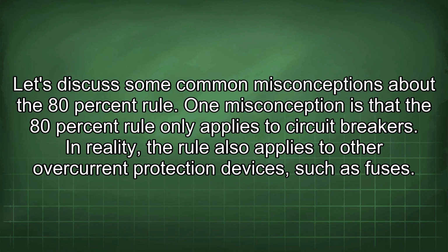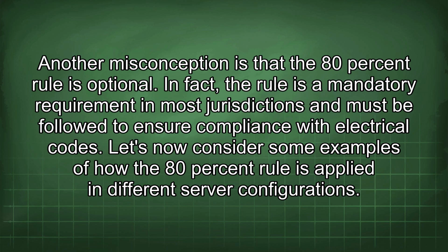Let's discuss some common misconceptions about the 80% rule. One misconception is that the 80% rule only applies to circuit breakers. In reality, the rule also applies to other overcurrent protection devices, such as fuses. Another misconception is that the 80% rule is optional. In fact, the rule is a mandatory requirement in most jurisdictions and must be followed to ensure compliance with electrical codes. Let's now consider some examples of how the 80% rule is applied in different server configurations.